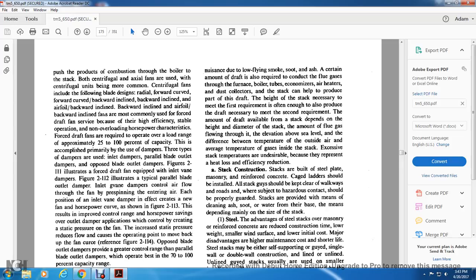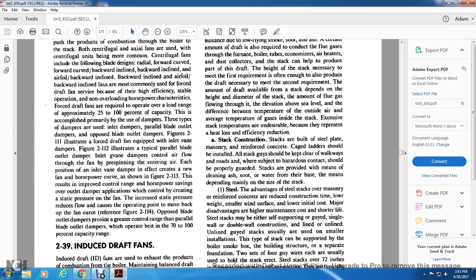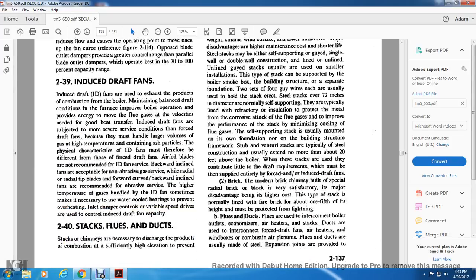The result is an improved control range and horsepower savings over outlet damper application, which controls by increasing the static pressure of the fan. This increased static pressure reduces the flow and causes the operating point to move back up the fan curve. Reference figure 2-114. Opposed blade outlet dampers provide a greater control range than parallel blade outlet dampers, which operate best in the 70 to 100% capacity range.